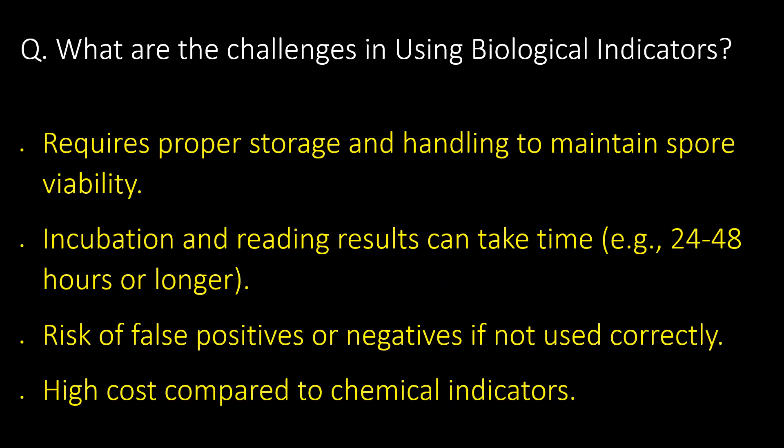What are the challenges in using biological indicators? They require proper storage and handling to maintain spore viability. Incubation and reading results can take time, for example 24 to 48 hours or longer. There is a risk of false positives and negatives if not used correctly. Biological indicators also have a high cost compared to chemical indicators.